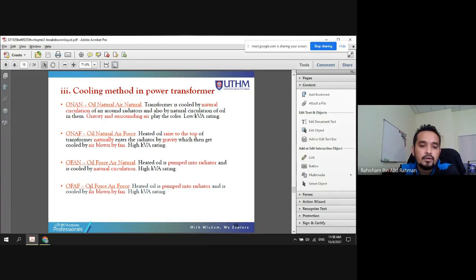By definition, you can see that we use a pump for both, and fan for the external. These are mostly for high kVA rating. ONAN is normally used for low kVA because it's less critical, meaning the heat generated from this low kVA is not that significant, so it just relies on natural cooling.